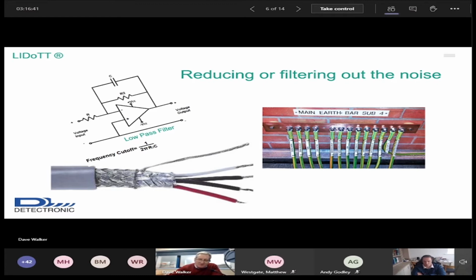Now, something that does tend to happen with the braided screen and connecting it to earth, if you're not experienced in earthing and screening of applications, is that everybody says, make sure you've screened it, make sure you put the screen to earth, and they screen both ends. Well, when you screen both ends of a cable to earth, you've effectively created yourself a very good antenna. And so you're not screening any more. What you're now doing is introducing a more susceptible application for receiving radio transmissions. You only have to read up about Marconi and what he did all those years ago. He made some fantastic antennas. So you've got to be careful that you don't end up screening both ends.